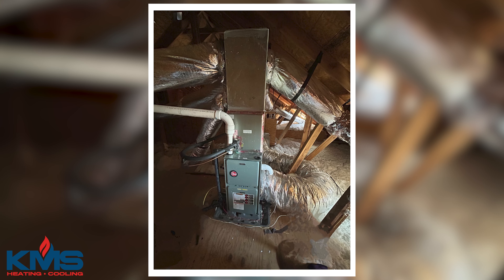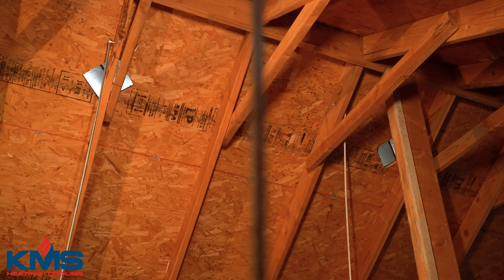This customer had a vertical stack inside the attic sitting on the attic deck, so as the unit was running it was making vibrations that would come through the ceiling. You always knew when the system was on — whether heating or cooling — because of the vibrations.